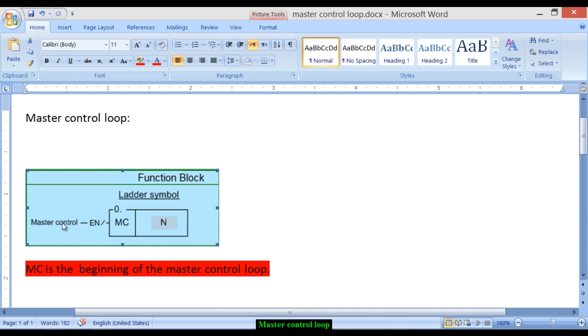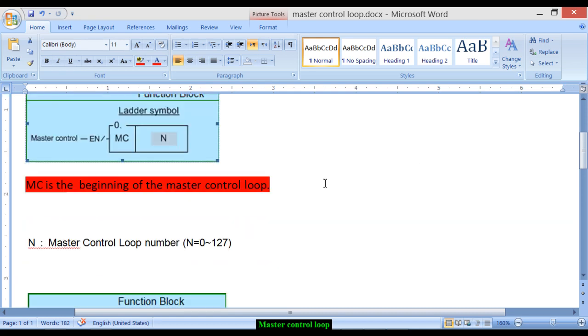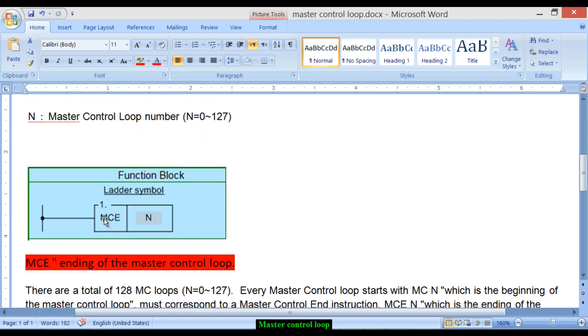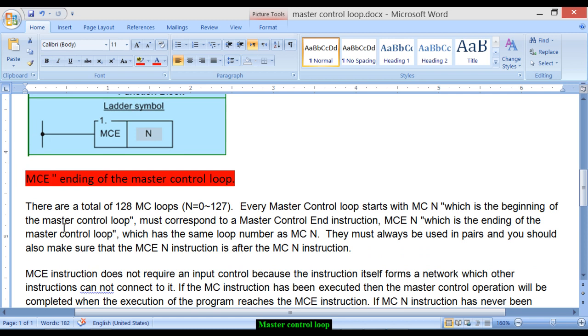The MC instruction has a master control enable signal EN. To make it 0 or 1, it always needs an input signal. That input signal can come from an external switch, an external sensor, the PLC's internal coils such as M0, M1, or M2, or it can be a control signal from SCADA. The MCE instruction, on the other hand, does not require any input signal.